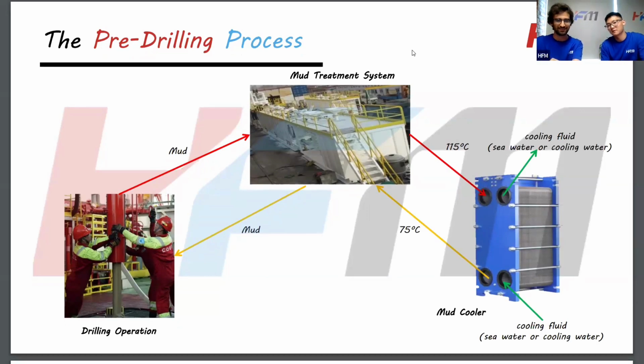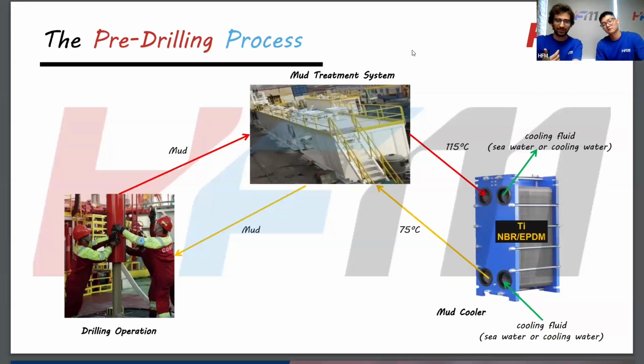So you mean the PHEs part of this system? Yeah, exactly. They are treated and then sent to the heat exchanger to reduce their temperature so they can be used again. As we talked about, the material is titanium, because many times there are corrosive materials that cannot be used otherwise. That's why titanium is a very good material for the plate of the heat exchanger, while the gasket can be nitrile rubber (NBR) or EPDM.